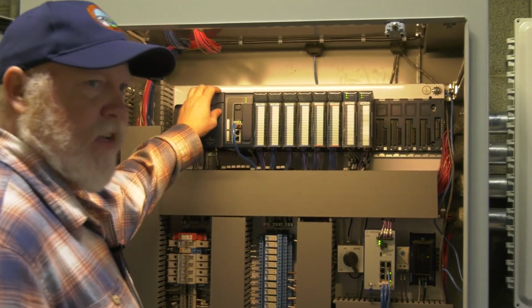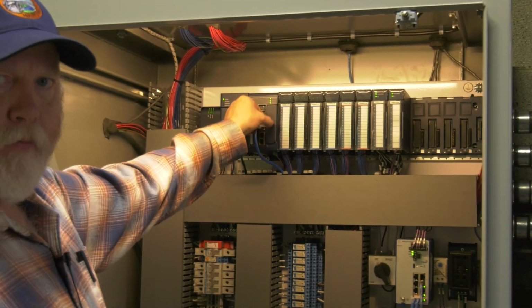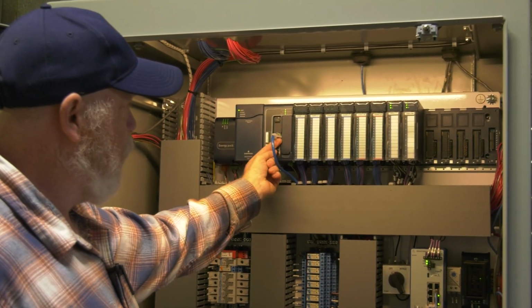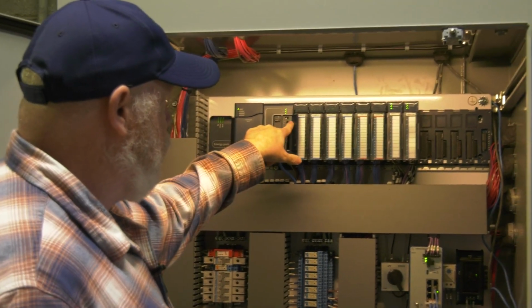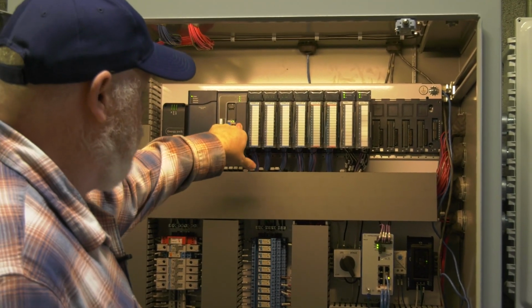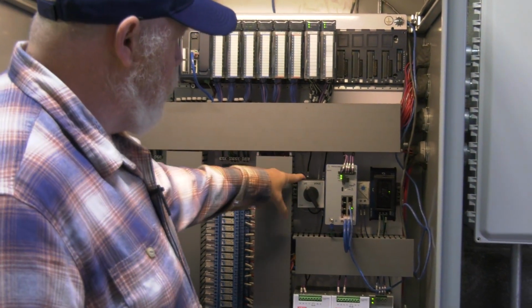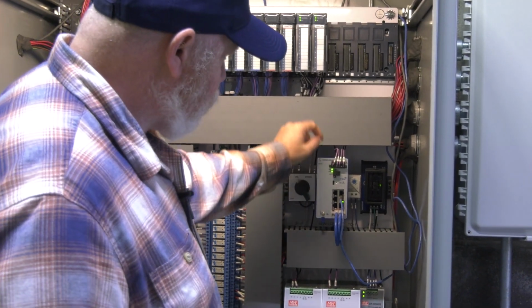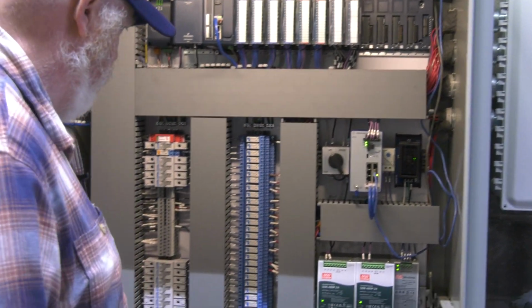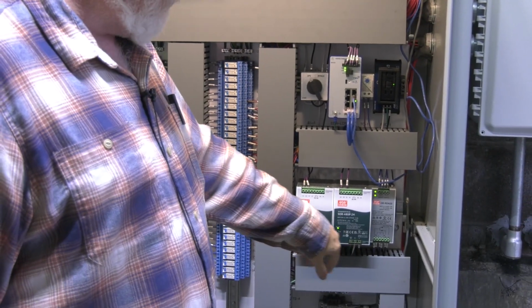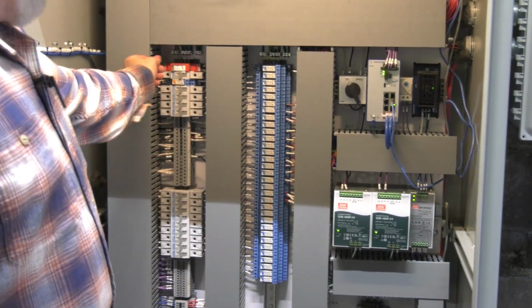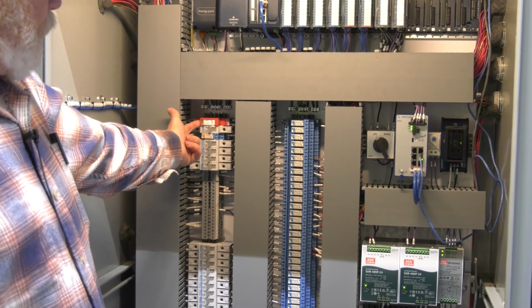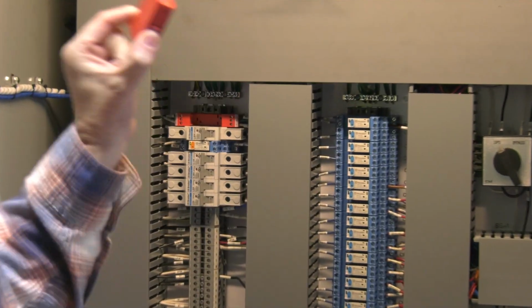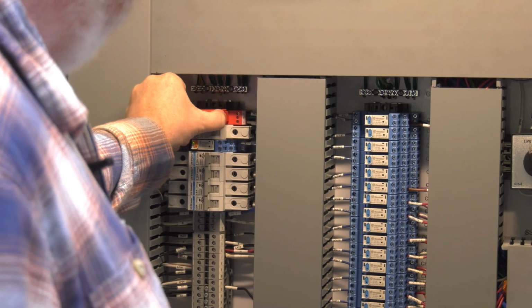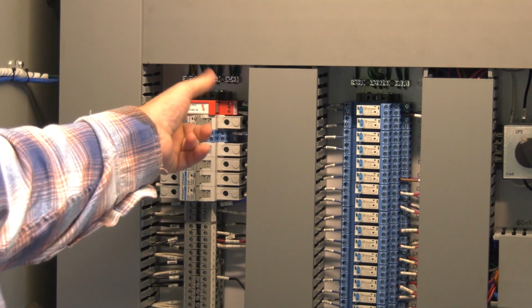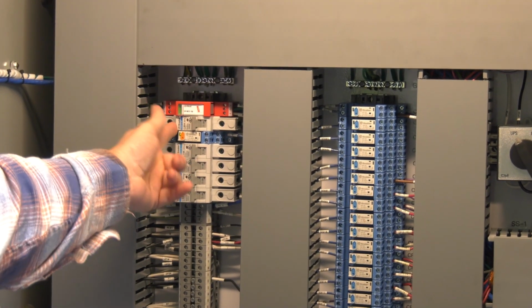All right, got PLC. Again, make sure that the switch in here is turned to on or run with IO. All righty, we got UPS bypass switch, Ethernet switch, redundant 24-volt power supplies, redundancy module, 120-volt surge suppressor, which is replaceable. This is your main circuit breaker. You kill 120 volts to the entire panel.